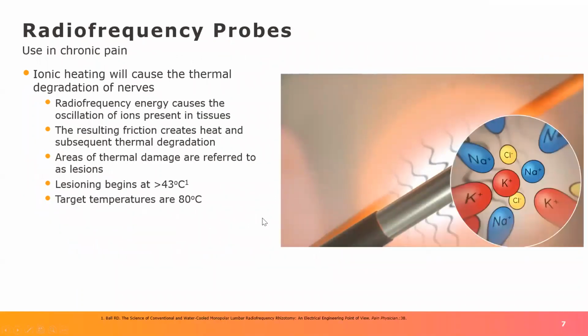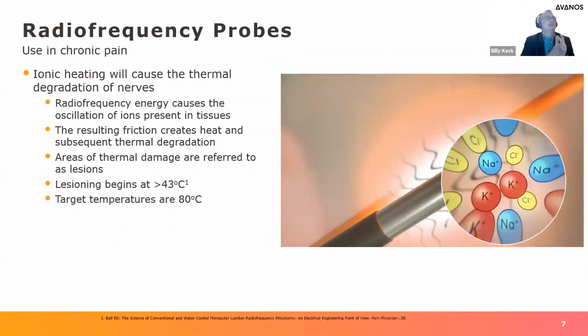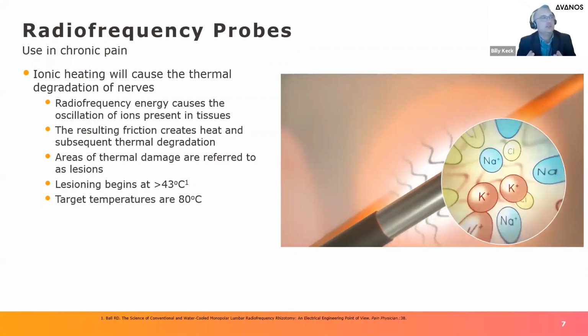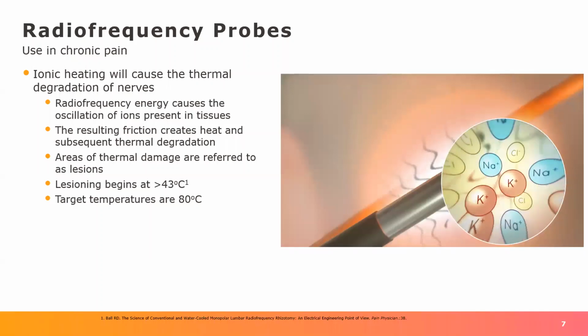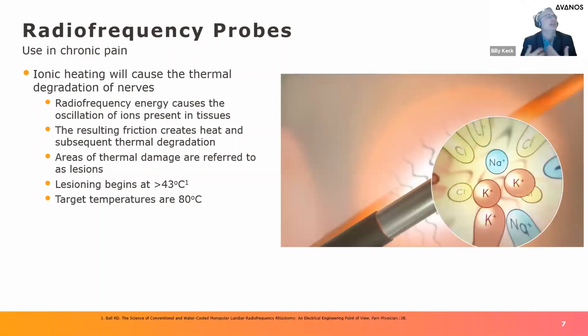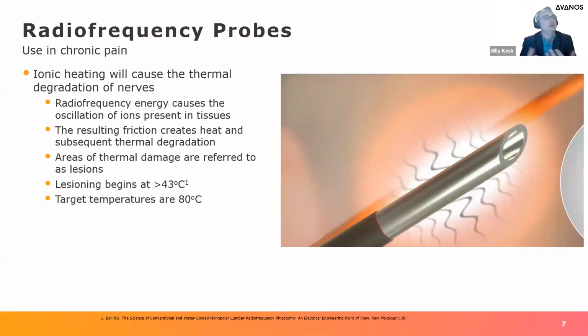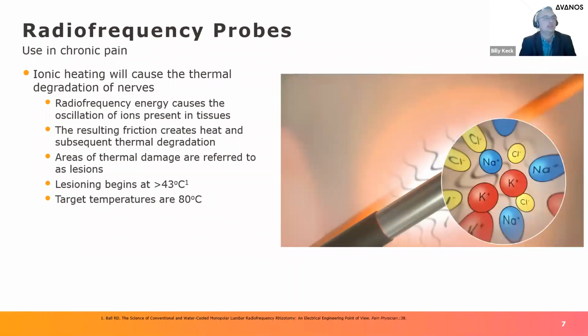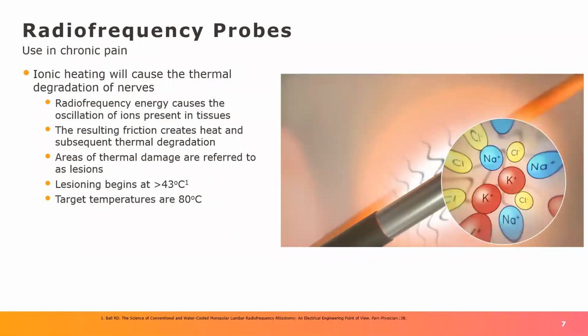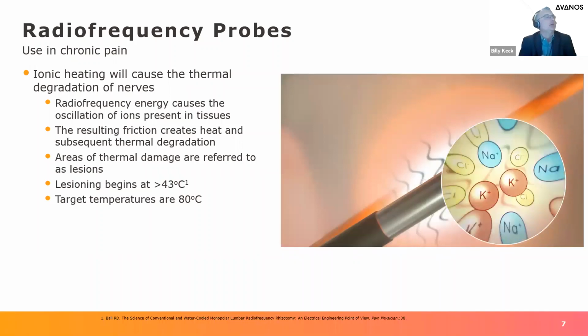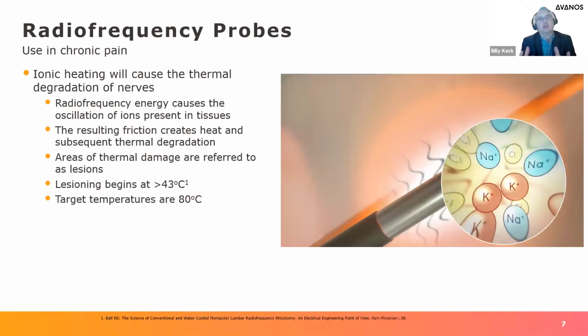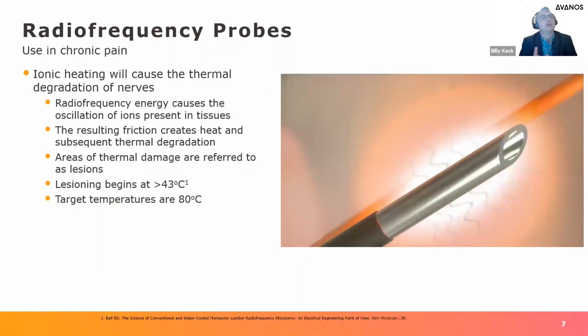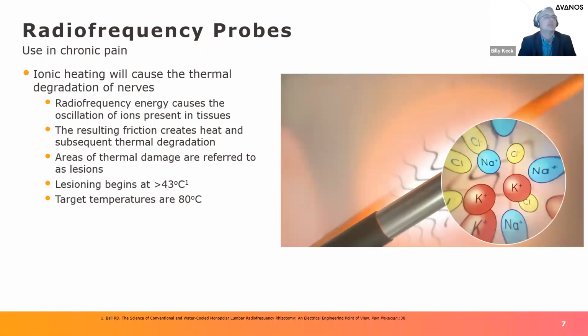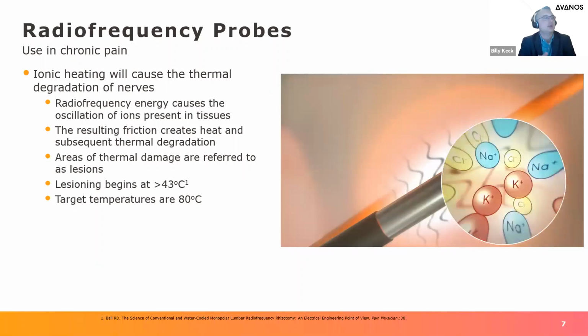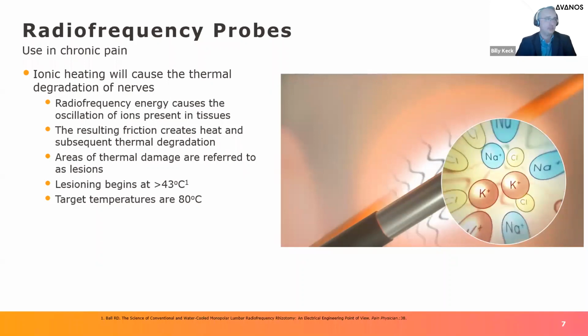So what is ionic heating? Basically, radiofrequency energy causes oscillations of ions within the tissues, and the resulting friction creates heat. If you generate enough heat, you can create temperatures in excess of 80 degrees Celsius, which is what is utilized to ablate the nerves. We call this area that has this heat a lesion. What's important to know is that lesioning actually begins at 43 degrees Celsius, but the target temperatures commonly utilized in clinical practice exceed 80 degrees.